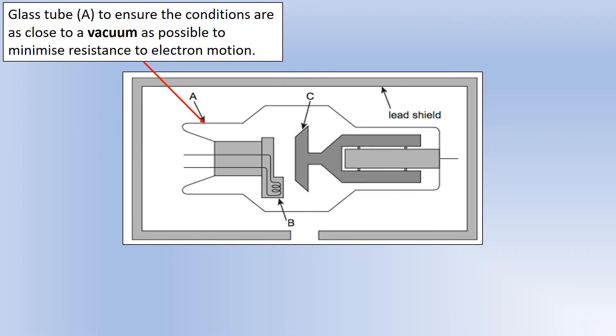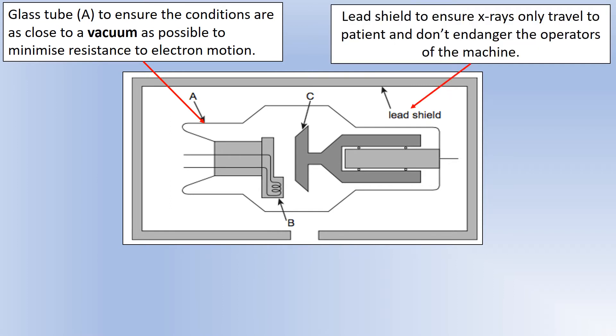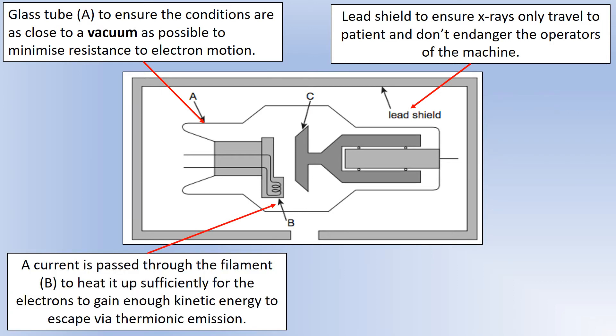The first part, labeled A, is a glass tube which creates a vacuum between the filament or cathode labeled B and the target or anode labeled C. We want this vacuum because we don't want the electrons we're producing to be impeded by gas atoms. The lead shield — the gray barrier visible all around with only one hole — ensures x-rays only travel in one direction, minimizing radiation risks to users and operators.